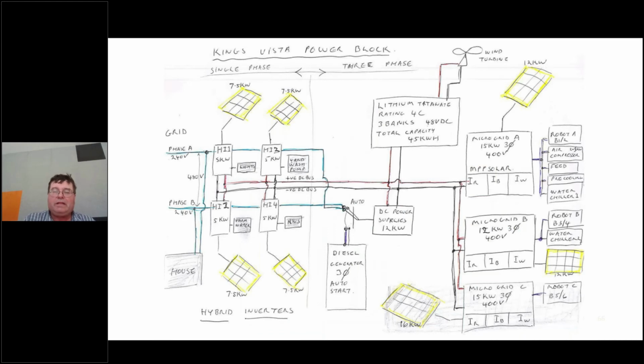This is the master plan of the power system. I basically run 3 microgrids now. So you'll see over on the right-hand side, microgrid A, microgrid B, microgrid C. They each have their own solar panels, all hooked to a common lithium titanate battery, wind turbine on top. There is a connection to the grid with hybrid inverters. But technically, our only way we get power from the grid to the robots at the moment is through the DC power supplies. None of the robots are connected directly to the grid. I do all my own power conditioning running off grid and isolated.